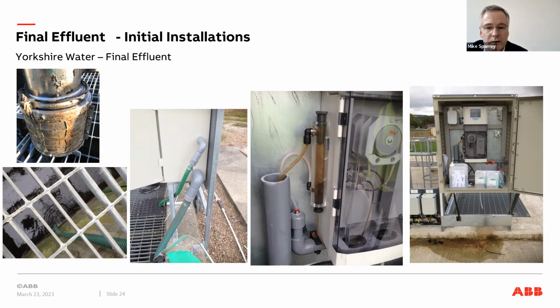We started off with a nylon filter, around 50 microns. Experience taught us we could go up to 100 microns, and we also moved to a stainless steel system. This was more robust and could be cleaned quickly and easily, which allowed the contractor and the water company to utilize the system effectively.